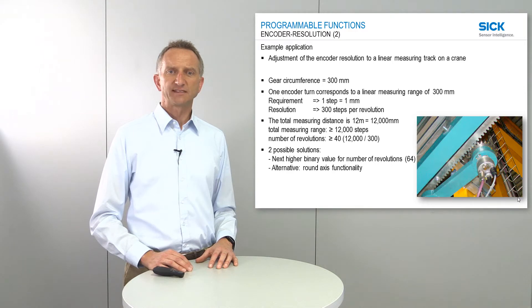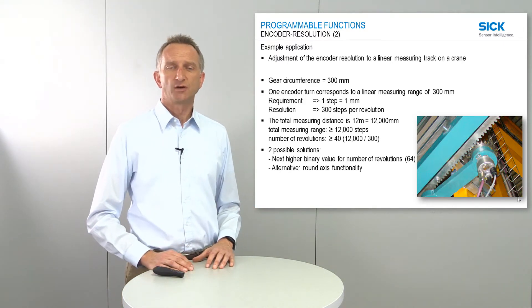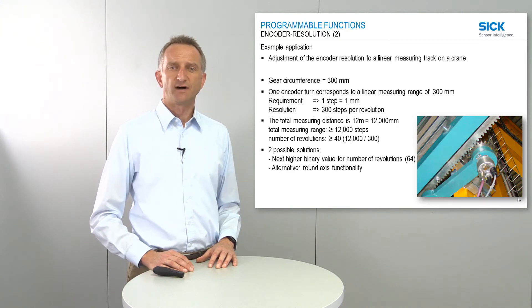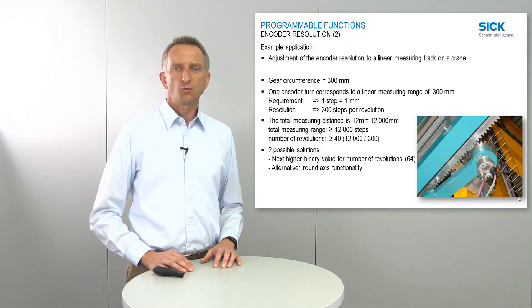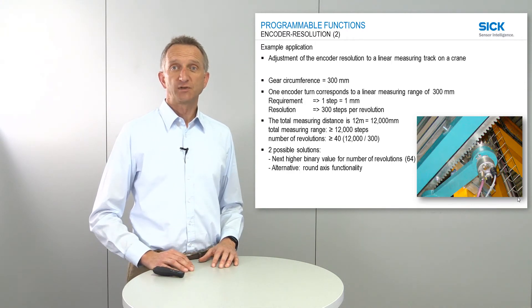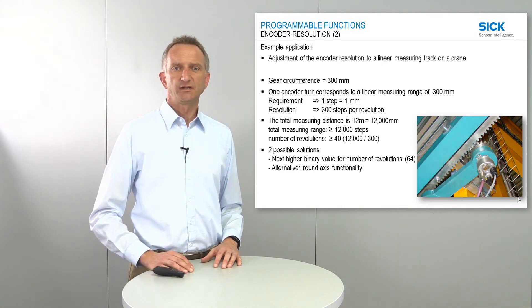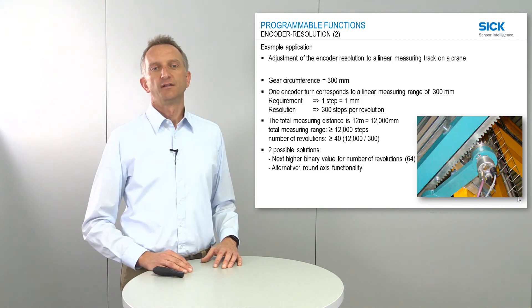The linear track overall has a length of 12 m, so our total measuring distance is 12,000 mm, equaling a total measuring range of 12,000 steps. To calculate the number of revolutions needed, we divide 12,000 by 300, which gives a result of 40 revolutions. With this result, we can either go to the next higher binary revolution value of 64, or alternatively set the scaling directly to the exact value of 40 revolutions using the so-called round axis functionality, which will be explained later.